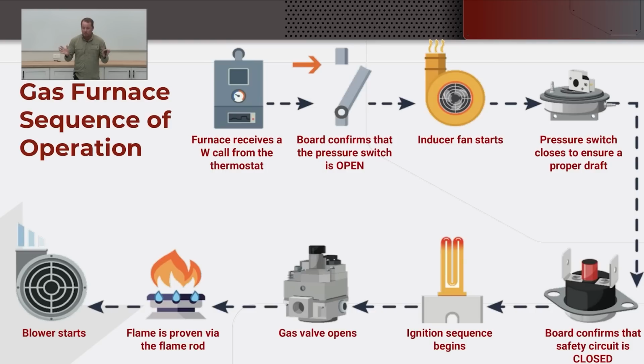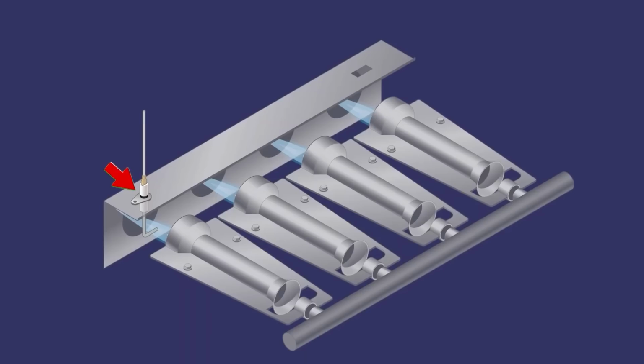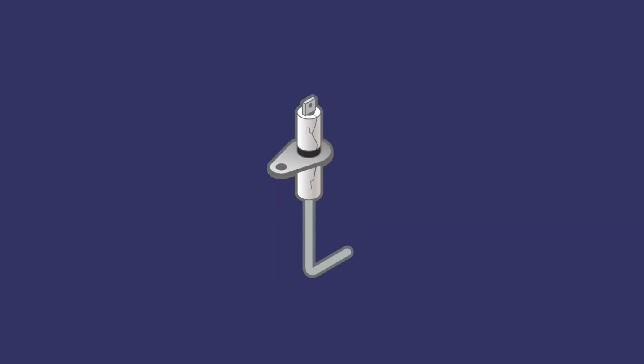It doesn't matter. The point is, in order for this whole thing to work, that rod needs to be immersed in flame. So it needs to be positioned correctly. It needs to not be broken. The ceramic shouldn't be broken, any of that stuff. It needs to be clean, so not covered in carbon, and the furnace needs to be well grounded.